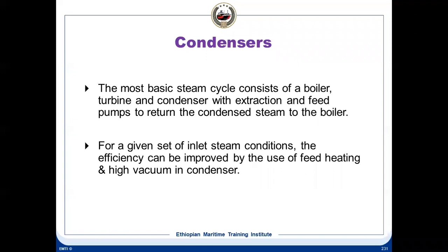And then from the condenser, you have these extraction and feed pumps to return the condensed steam, that is, return the condensate back to the boiler. And for a given set of inlet steam conditions, the efficiency can be improved by the use of feed heating, as we just saw with the deaerator cum feed heater, and by using high vacuum in a condenser.